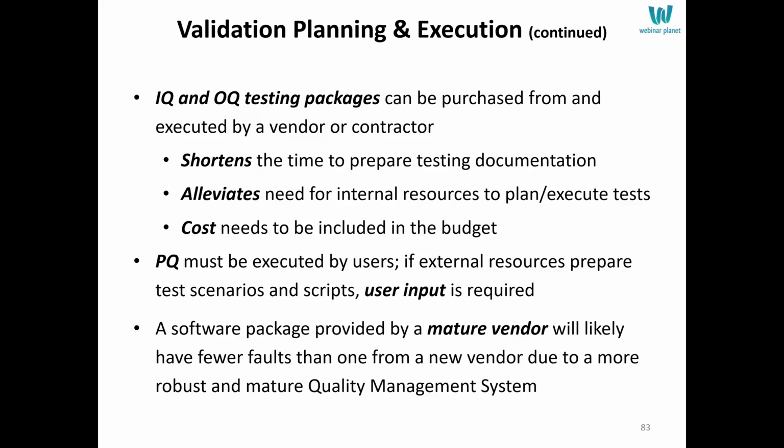You must review and approve all of their work. Review and approve their plans before they execute those protocols, and then review and approve the work that they collect. So this can be a big time savings, but it comes at a cost. However, when you get to PQ, you can have external resources prepare your PQ protocol and summary report.